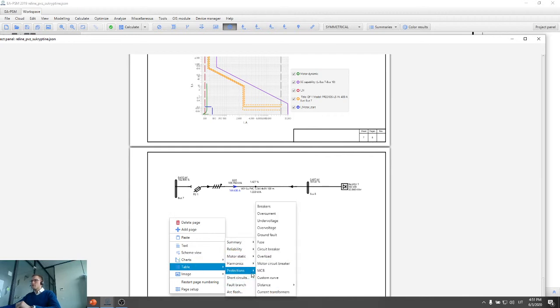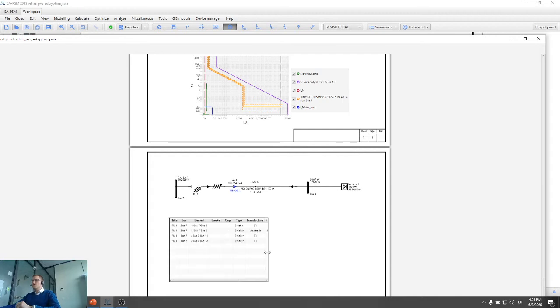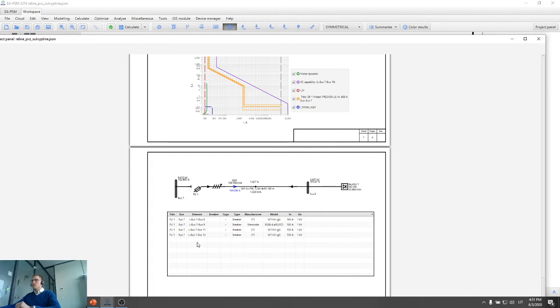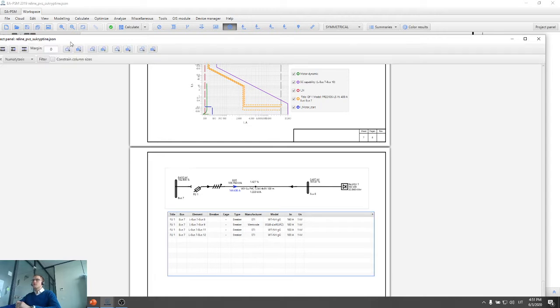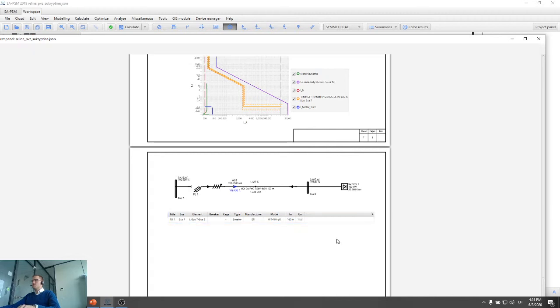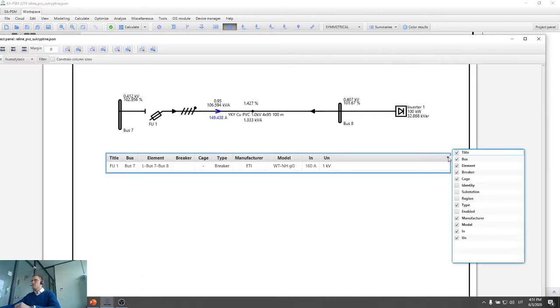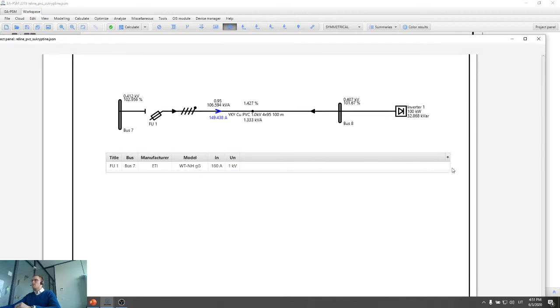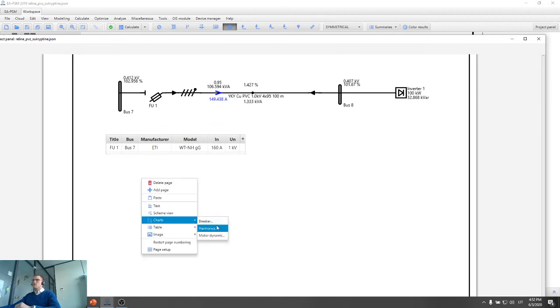So let's go to protection, fuse. Here's the list of all the fuses in the network. Basically all of them are connected to bus 7, so I can also use a filter to select the particular fuse. Yeah. Some of the columns of the fuse are not needed, so I'll just simply disconnect them. So let's say I don't need information about the element, breaker, cage, type. Maybe only this data is interesting for me. Yeah, so here's the information about the fuse.